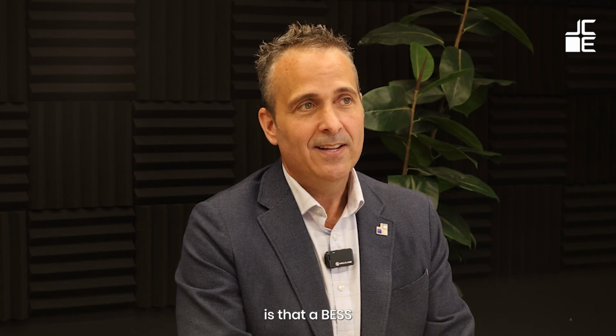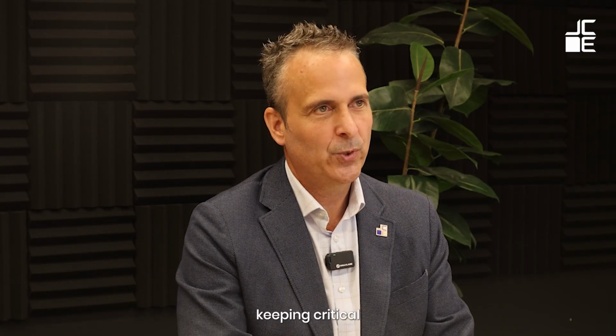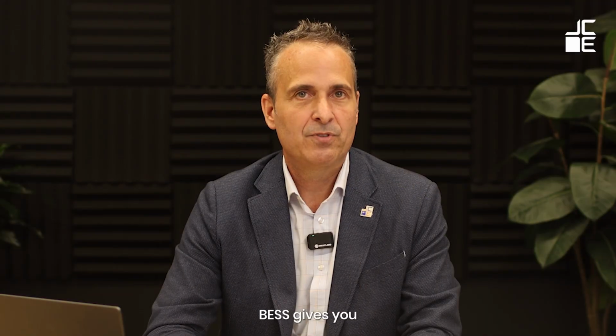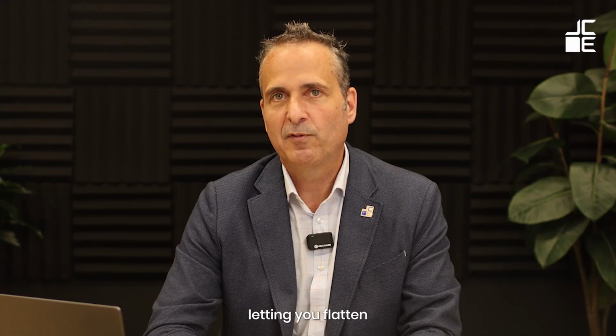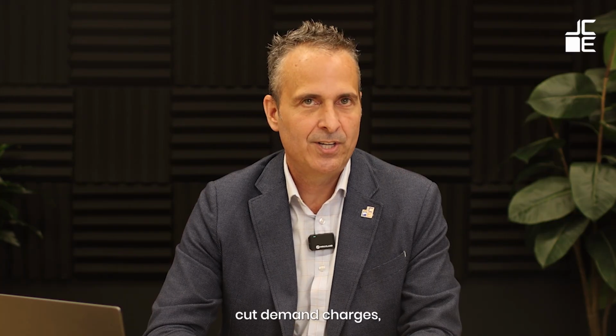What we've seen today is that a BESS with either a UPS or PCS conversion have different capabilities. UPS protects your facility against downtime, keeping critical loads safe when even milliseconds matter. BESS gives you control over costs, letting you flatten peaks, cut demand charges, and participate in grid programs. If grid interruptions cause your facility nuisance and expensive downtime, a UPS solution with extended battery duration or a hybrid approach makes the most sense.